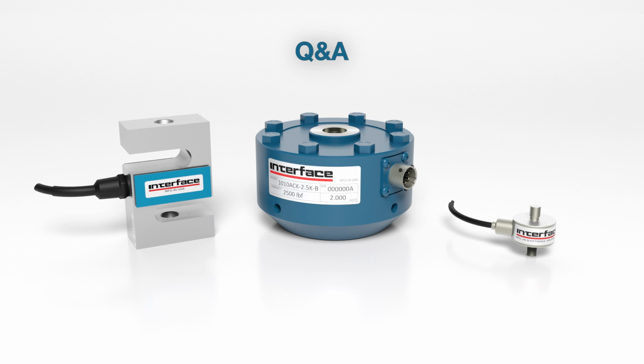We use different classes depending on the capacity. Typically, if it's a lower capacity, it's going to have a finer thread. Typically we don't use coarse, but it could go from a Class 3 to a standard thread, maybe on a larger capacity. But the data sheet's going to refer to that, and obviously you'd want to use a similar type of thread on whatever it is you're mating the load cell with.